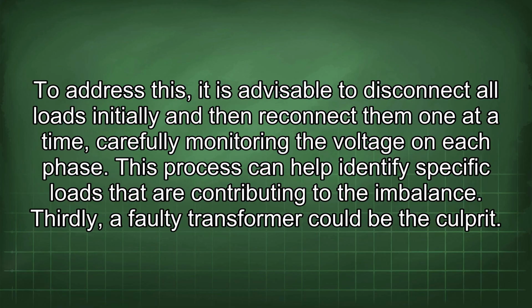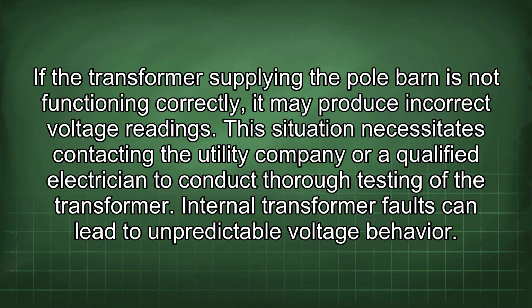Thirdly, a faulty transformer could be the culprit. If the transformer supplying the pole barn is not functioning correctly, it may produce incorrect voltage readings. This situation necessitates contacting the utility company or a qualified electrician to conduct thorough testing of the transformer. Internal transformer faults can lead to unpredictable voltage behavior.